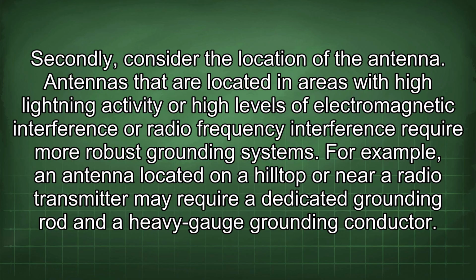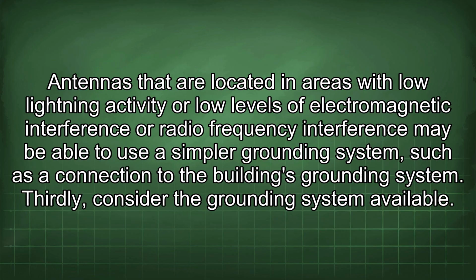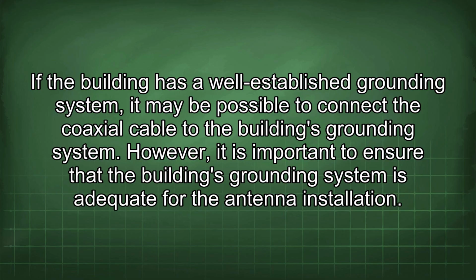Secondly, consider the location of the antenna. Antennas that are located in areas with high lightning activity or high levels of electromagnetic interference or radio frequency interference require more robust grounding systems. For example, an antenna located on a hilltop or near a radio transmitter may require a dedicated grounding rod and a heavy-gauge grounding conductor. Antennas that are located in areas with low lightning activity or low levels of electromagnetic interference or radio frequency interference may be able to use a simpler grounding system, such as a connection to the building's grounding system. Thirdly, consider the grounding system available. If the building has a well-established grounding system, it may be possible to connect the coaxial cable to the building's grounding system. However, it is important to ensure that the building's grounding system is adequate for the antenna installation.